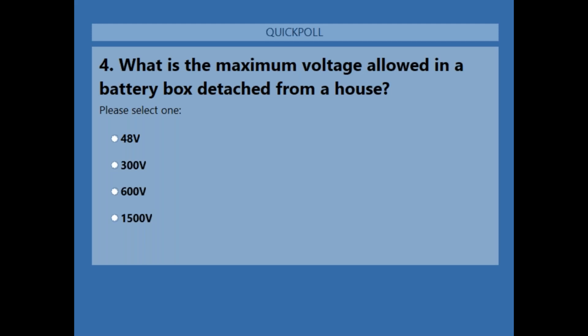Because as you increase your voltage, you're decreasing your amperage, and voltage is more constrained by, say, the jacket of the cable. You can be fine right up to 600 volts, but if you have a 600 volt device and you go a couple volts more than 600, it'll pop, almost like the bursting of a water balloon. Whereas amperage is more of a slower burn. If you exceed the amperage of the system, the device might not fail immediately. It might run hot, it might start to smolder, and then it might catch on fire, but it's not an instantaneous kind of disaster for a slight over amperage like it is over voltage.